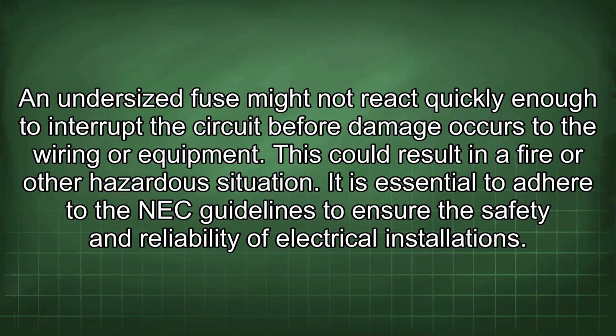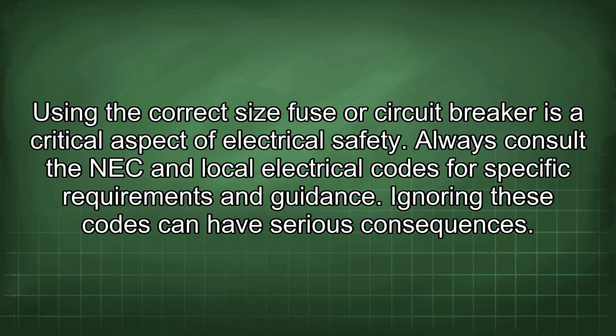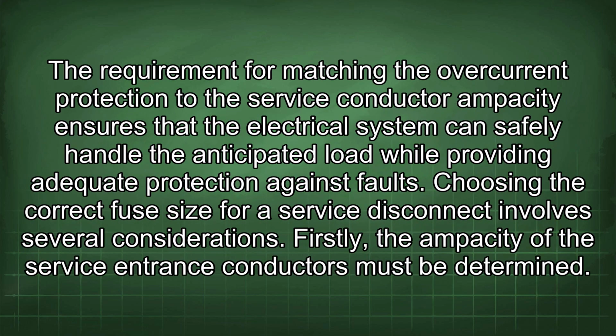It is essential to adhere to the NEC guidelines to ensure the safety and reliability of electrical installations. Using the correct size fuse or circuit breaker is a critical aspect of electrical safety. Always consult the NEC and local electrical codes for specific requirements and guidance. Ignoring these codes can have serious consequences. The requirement for matching the overcurrent protection to the service conductor ampacity ensures that the electrical system can safely handle the anticipated load while providing adequate protection against faults.